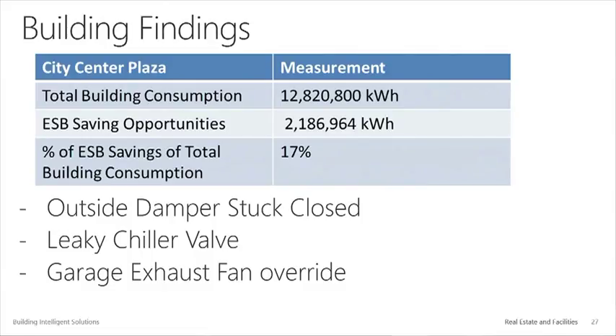In the basement, we have 7 layers of parking garage. So in the very basement of this building, the sewer pump had some problems. So what we did was we took all the exhaust fans in that building and put them to manual, to exhaust all the air out of the building while we made the repairs. That was about a year ago. Nobody ever caught that we left it in manual.